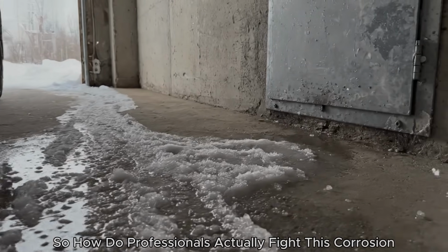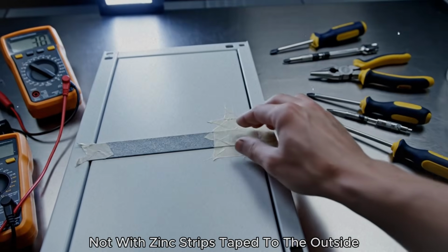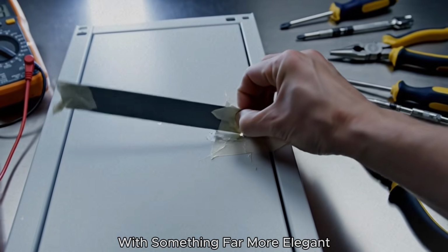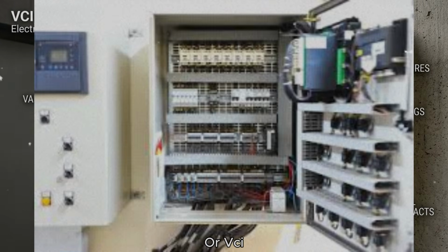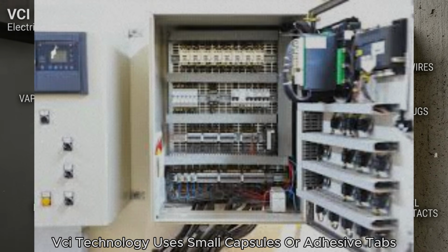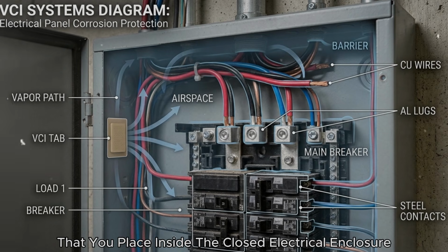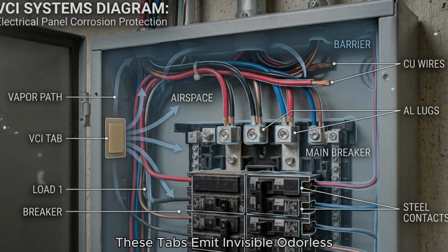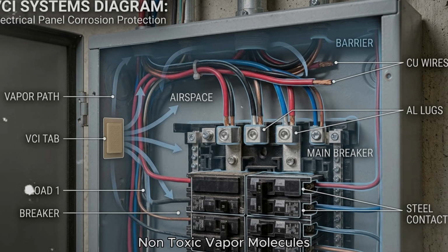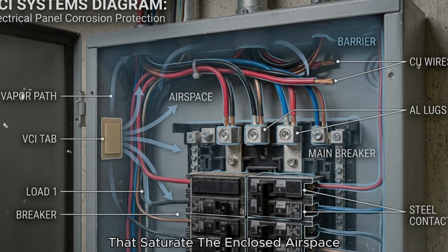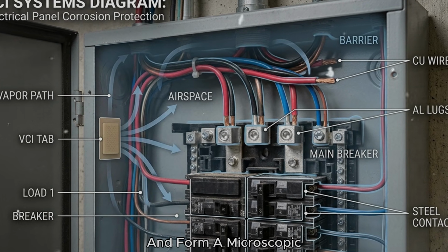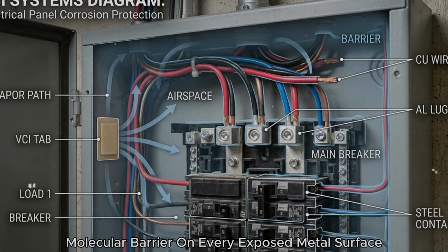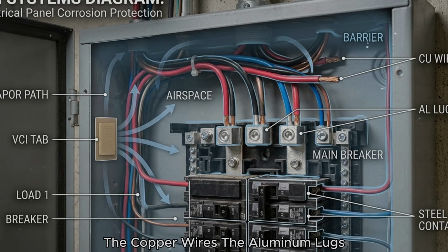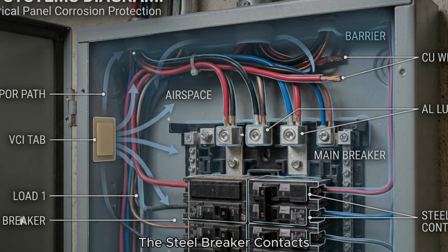So how do professionals actually fight this corrosion? Not with zinc strips taped to the outside, but with something far more elegant: vapor corrosion inhibitors, or VCI. VCI technology uses small capsules or adhesive tabs that you place inside the closed electrical enclosure. These tabs emit invisible, odorless, non-toxic vapor molecules that saturate the enclosed airspace and form a microscopic molecular barrier on every exposed metal surface: the copper wires, the aluminum lugs, the steel breaker contacts.